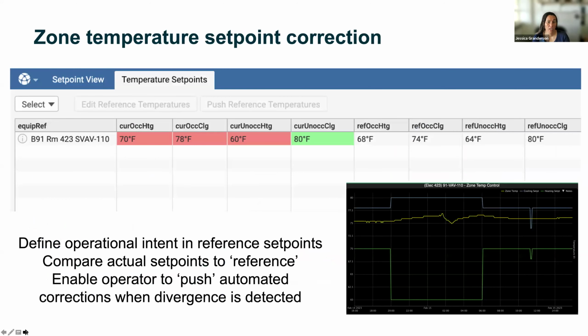Since I have the time, I want to give a couple of other examples, zooming out to all of the things that we can do when we have two-way capability and enhanced logic with our fault diagnostic systems. I'm going to show a couple other examples as implemented by Berkeley Lab's operational team, who run all of the facilities here at our laboratory site. This is zone temperature set point correction according to operational policies. Operators may change zone temperature set points for all kinds of reasons. For a central energy management or facilities team, this can be monitored and corrected back to the actual operational policy intent.